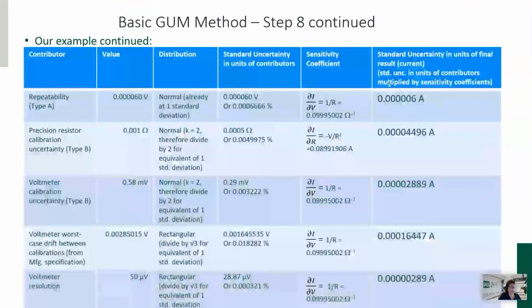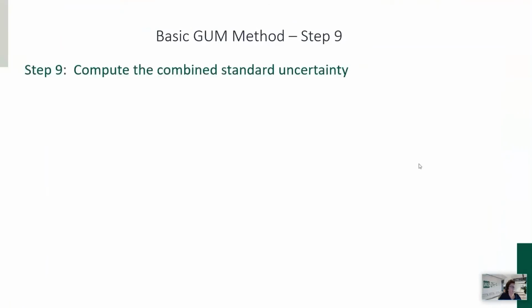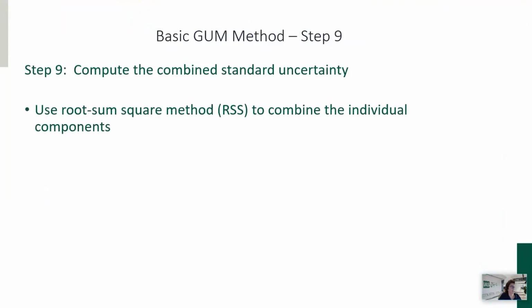So now we have all the standard uncertainties in the same units, and we compute the combined standard uncertainty. That is done assuming there's no correlation between the contributors, using a root sum square method to combine them. If they were all correlated, we would just do a straightforward addition and come up with a much larger uncertainty.